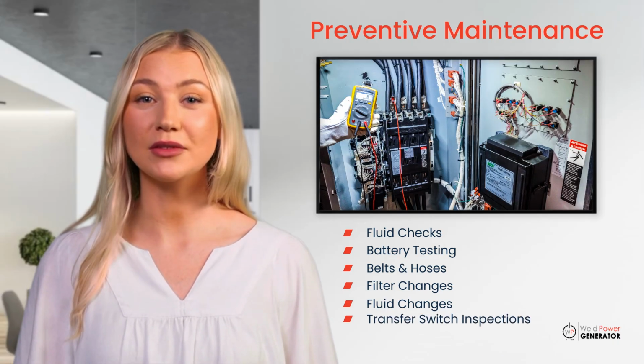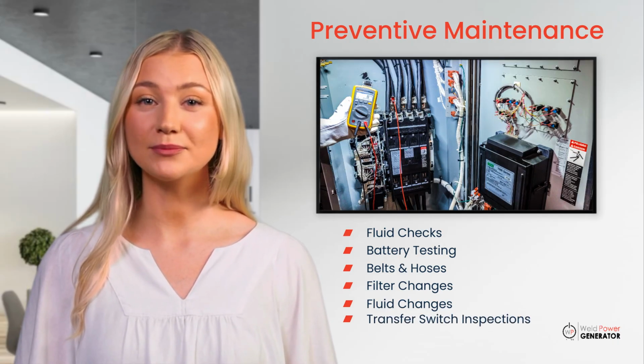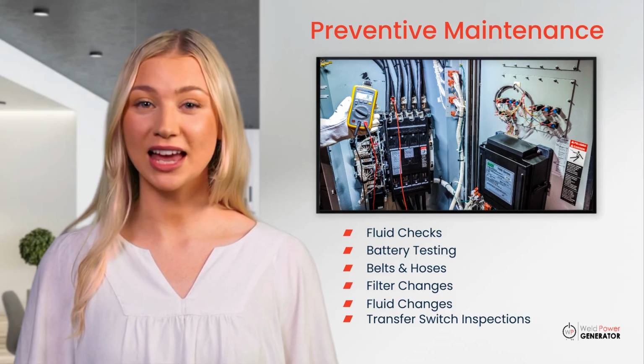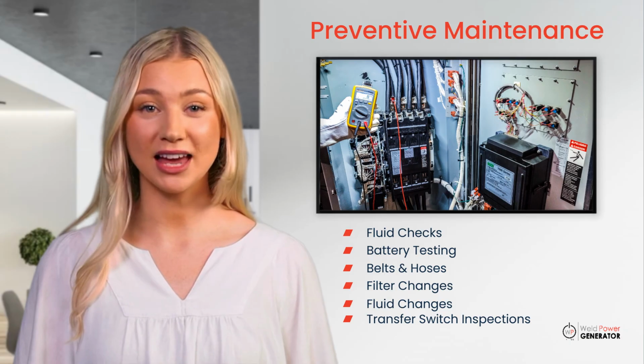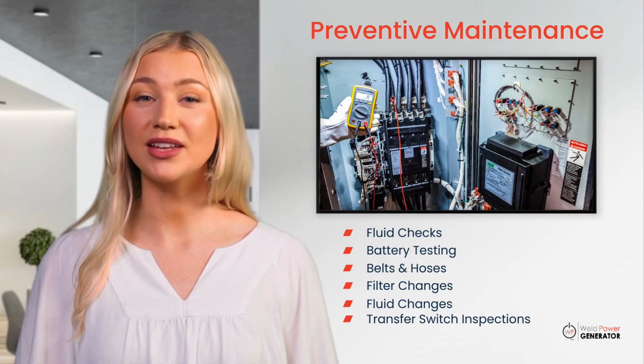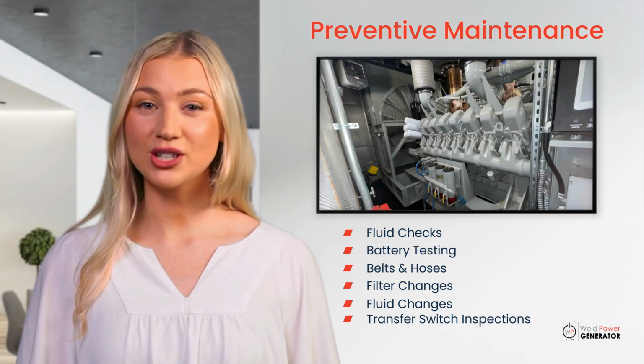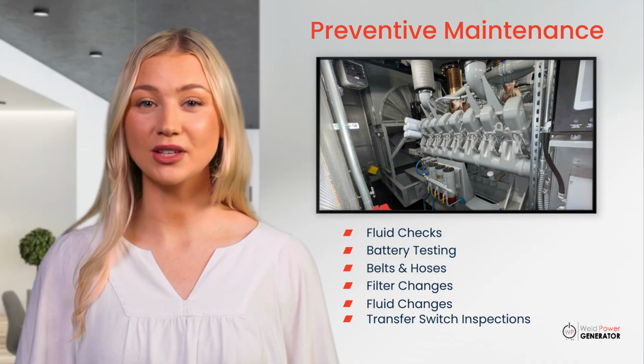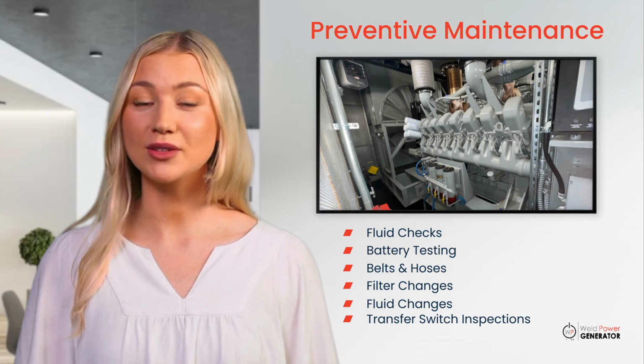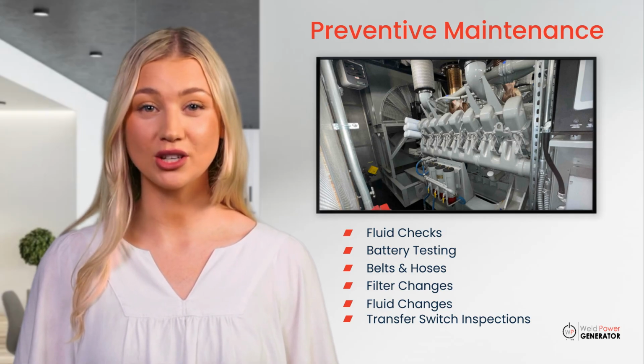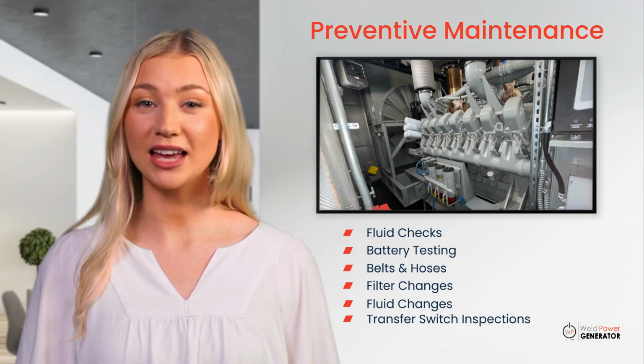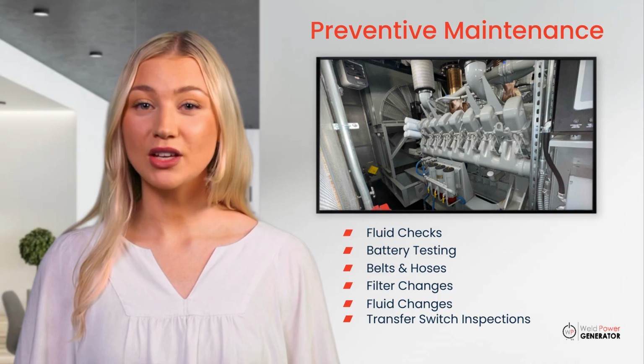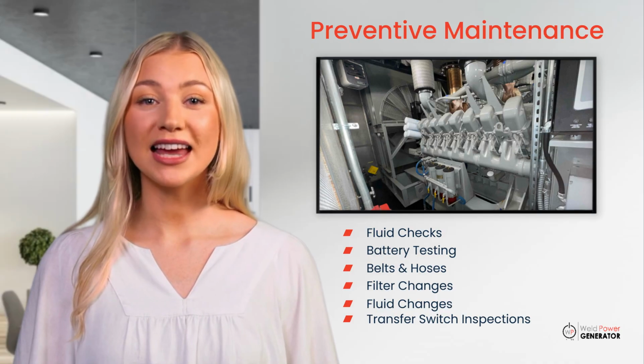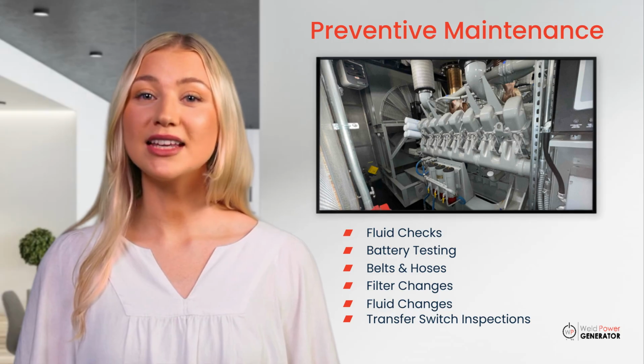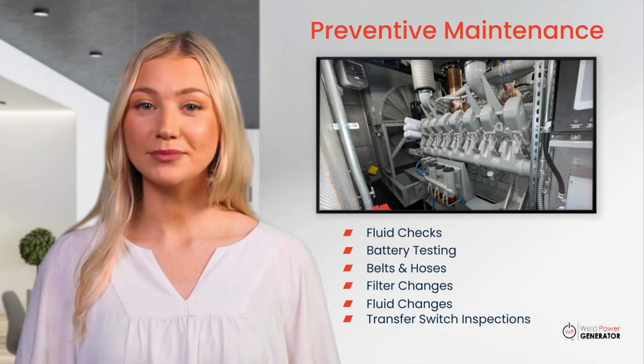Transfer switch inspection. The generator is only half the system. The automatic transfer switch, ATS, must be inspected, exercised, and tested as part of every PM program. Commercial generators should have preventative maintenance performed at least once every 6 months. More frequent inspections are recommended for mission-critical and life safety generators. Frequent inspections allow issues to be caught early and extend the generator lifespan.